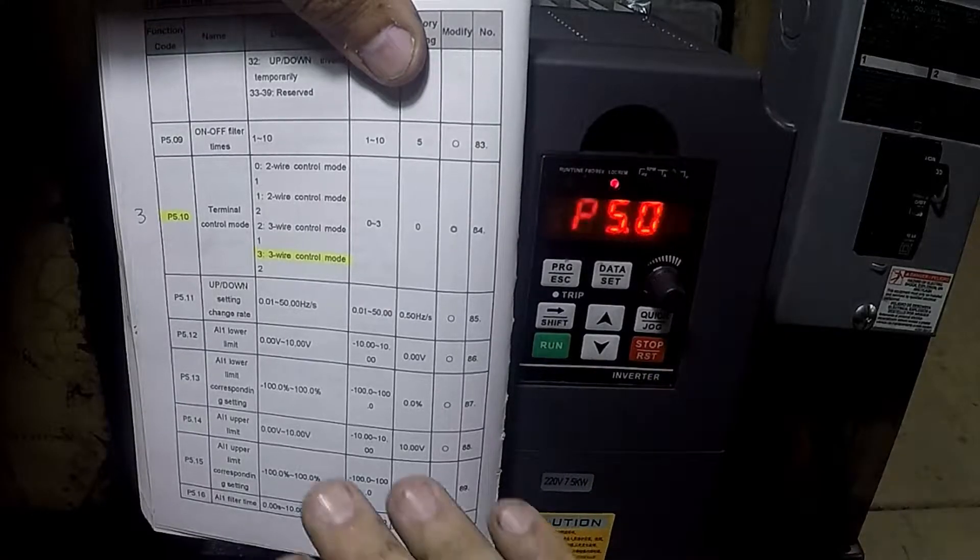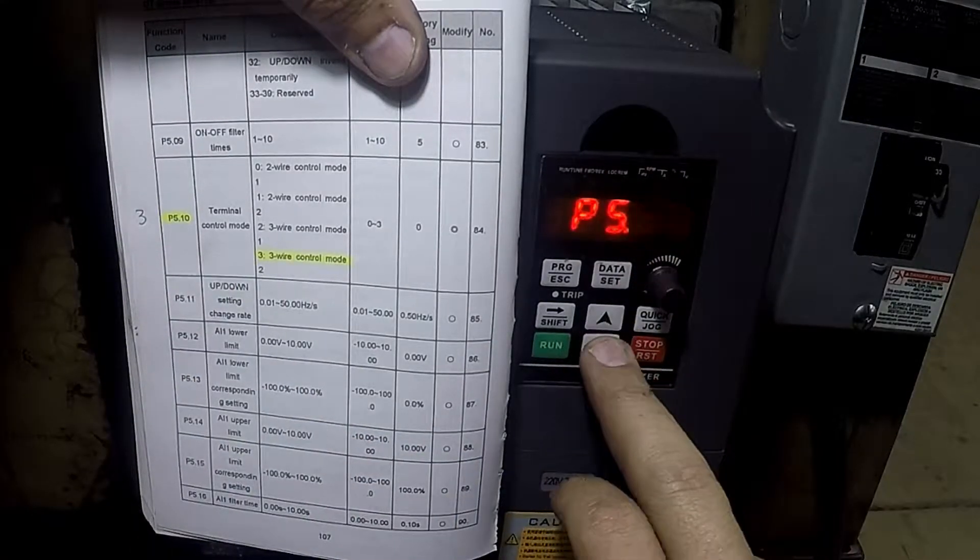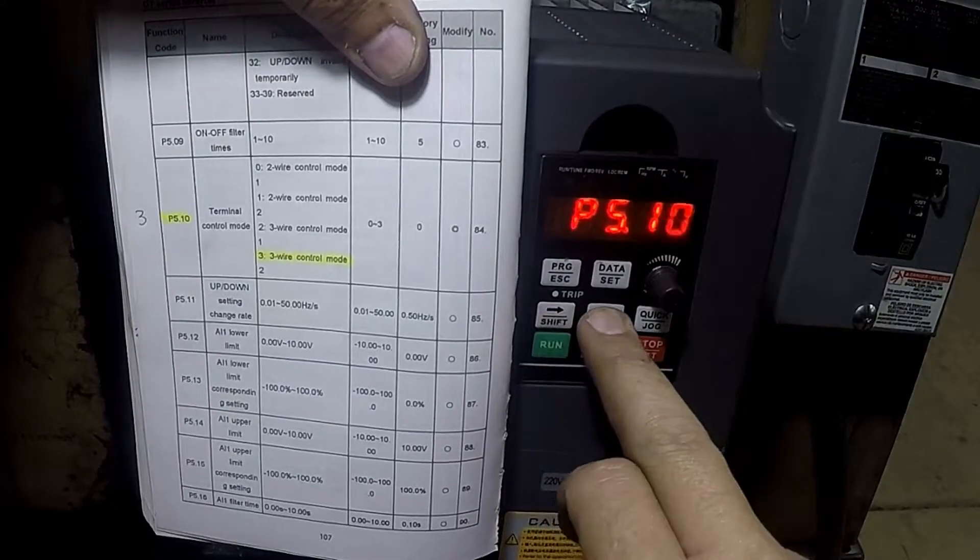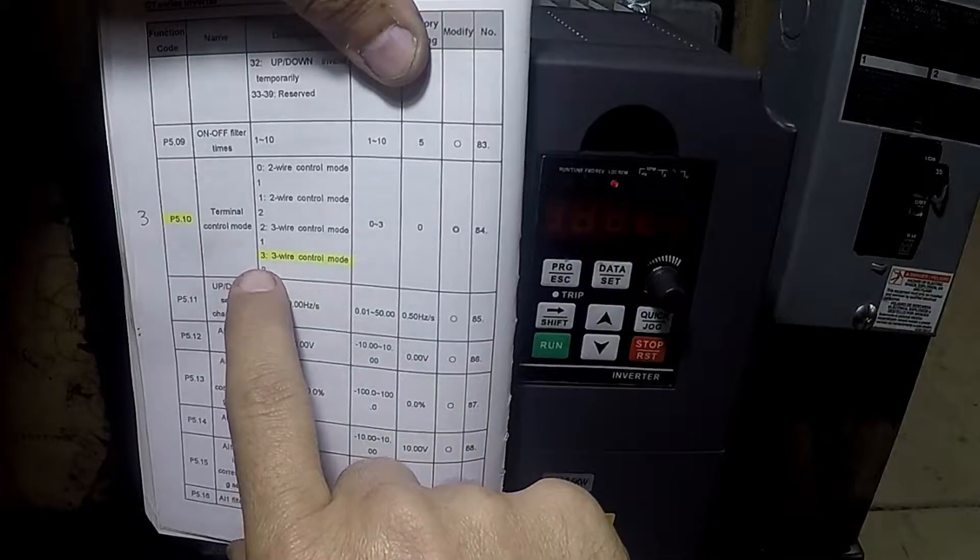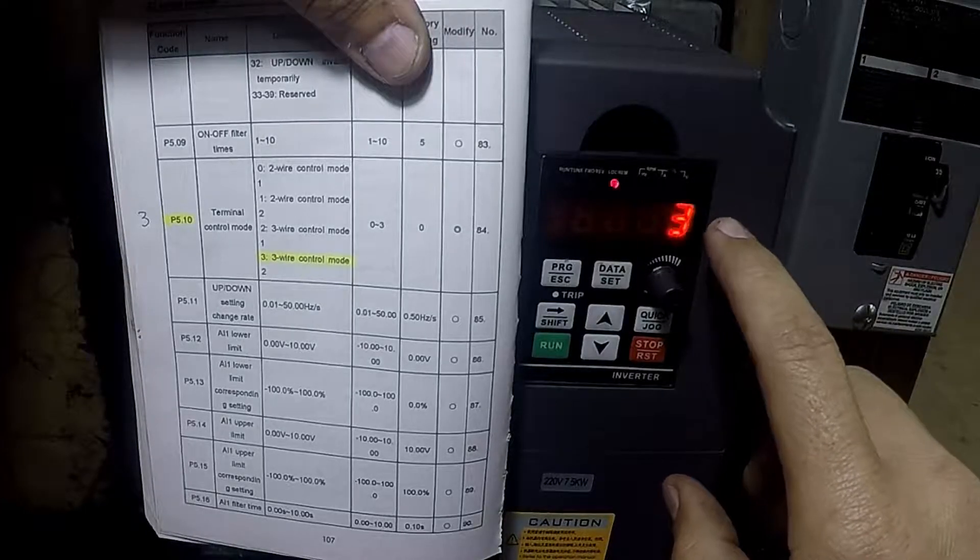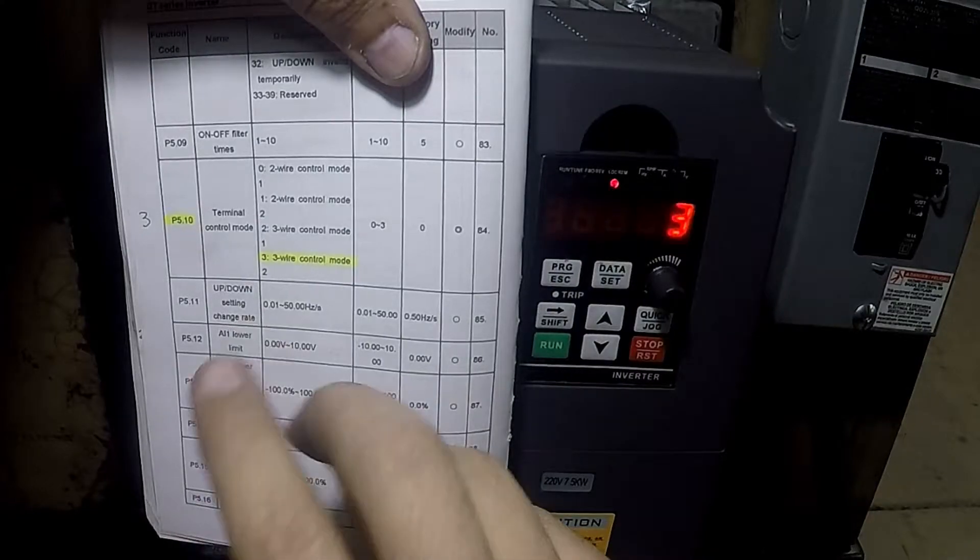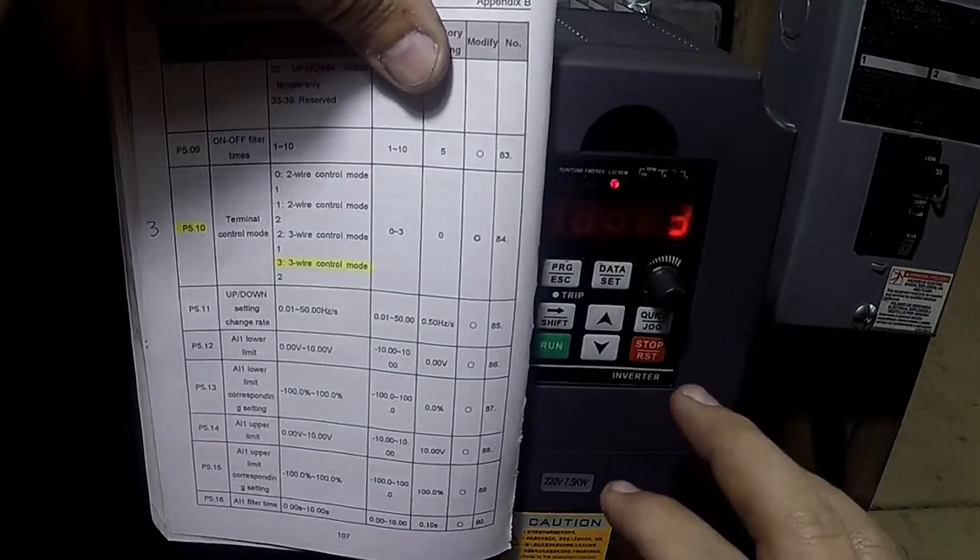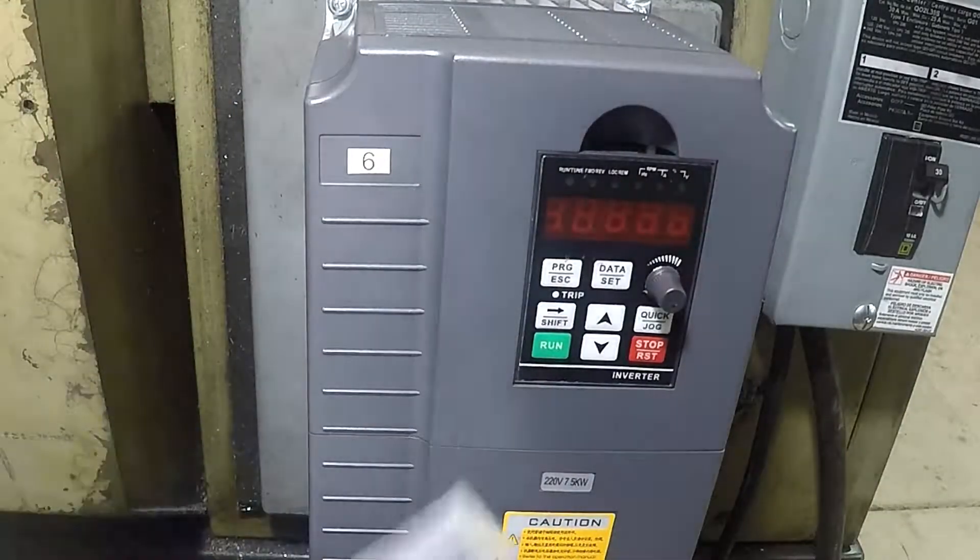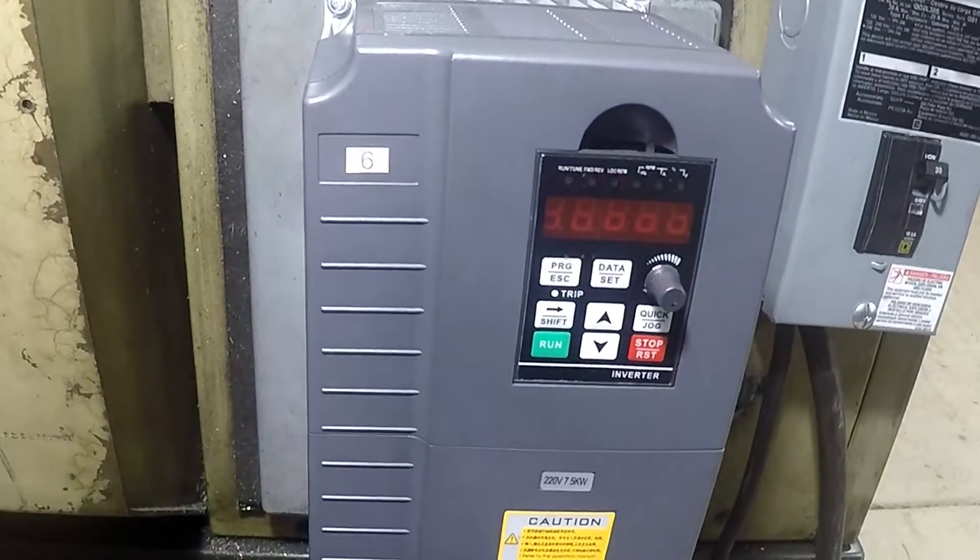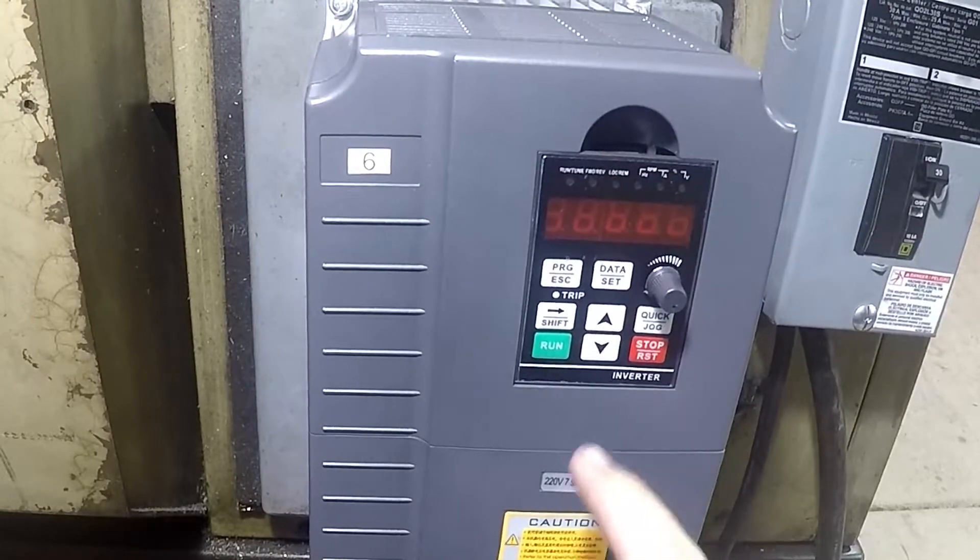And the final setting after setting number three is P5-10 which I have set to three. If you just got to this part of the video and you're wondering why we set it to three, you'll have to jump back previous in the video where I kind of went over a little bit of the different schematics and stuff. And that's the basic setup of how to program this VFD to be just a dumb single phase to three-phase conversion with the button panel actually functional.